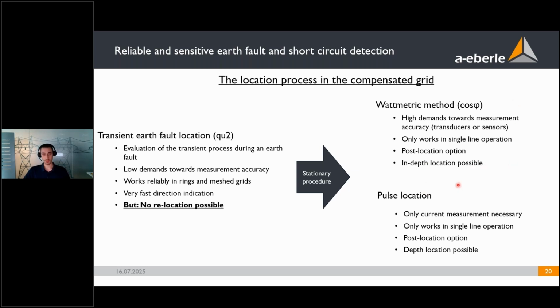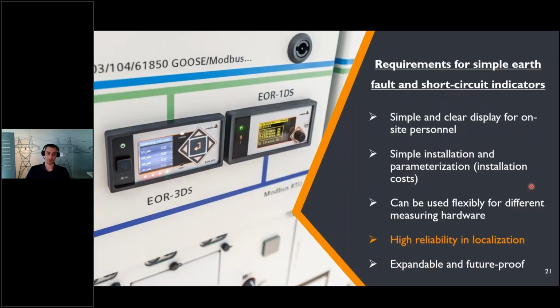Or you could also use the pulse location. Of course, for this you would need the possibility to send a pulse through your grid. But if you do have this possibility, then for the pulse location, you will only need current measurement inside your station. It only works in single line operation as well. You do have the post location option since it's a stationary procedure, and again, in-depth location is possible. So this fulfills the requirement of high reliability in localization.